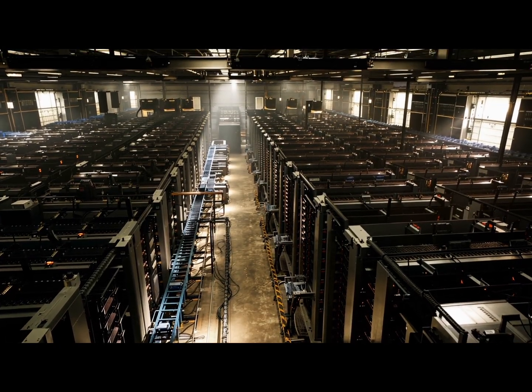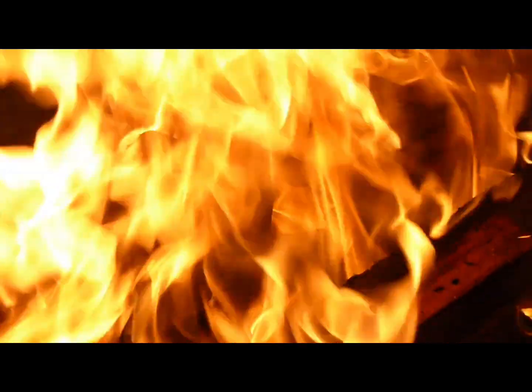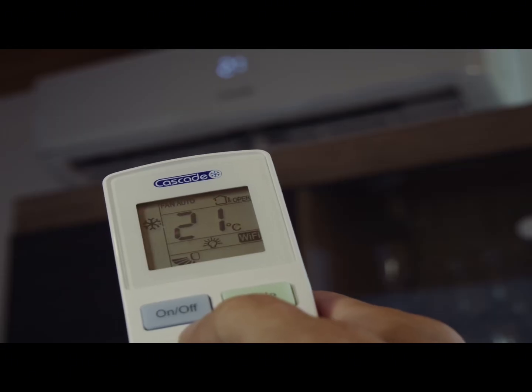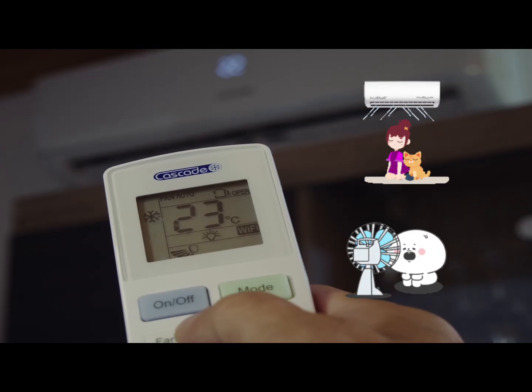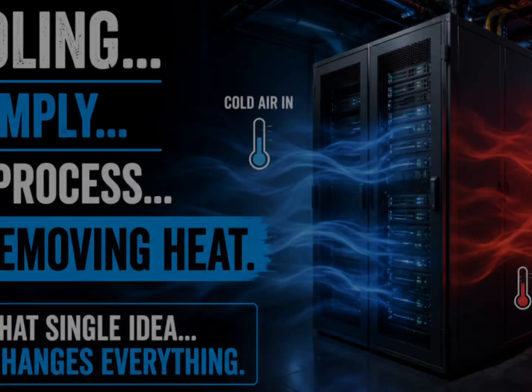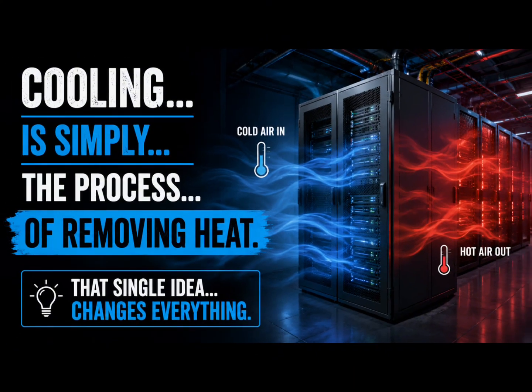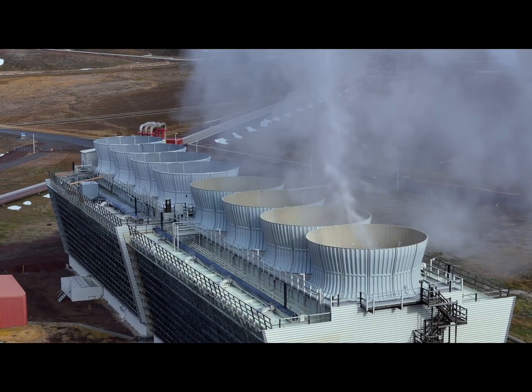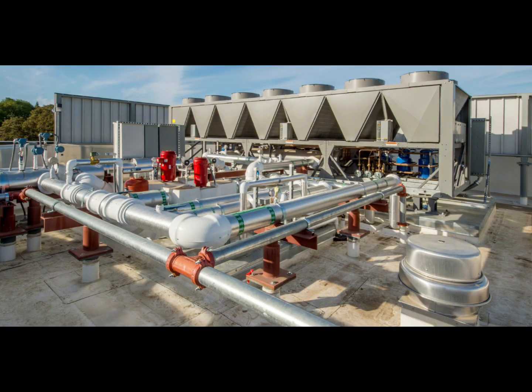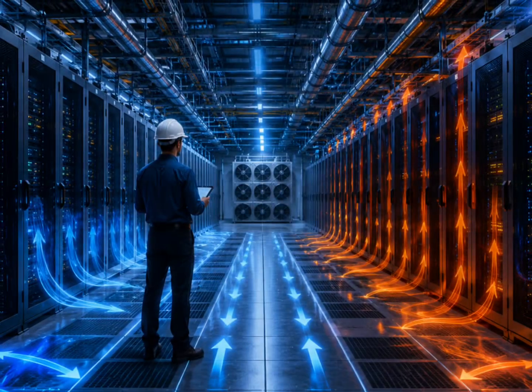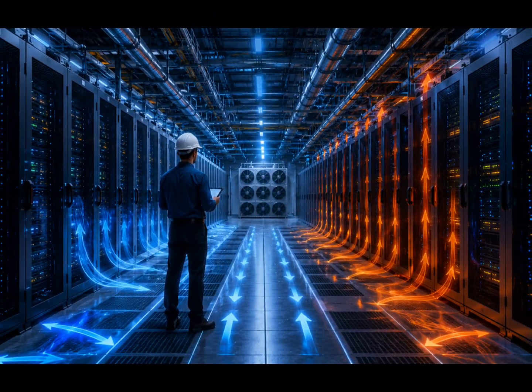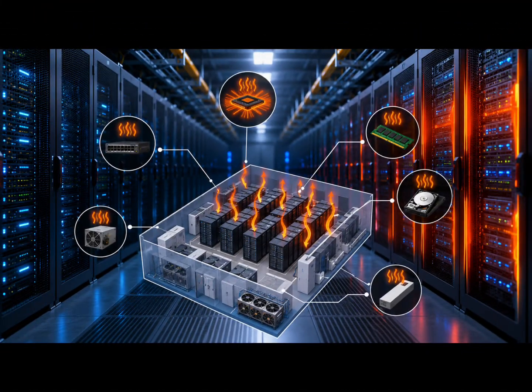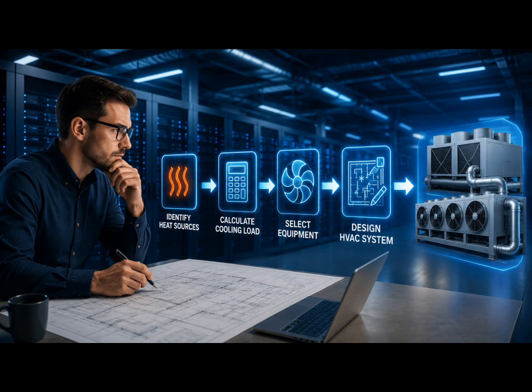The answer begins with one simple question. Where is the heat coming from? Many people believe cooling means producing cold air. It doesn't. Cooling is simply the process of removing heat. That single idea changes everything. Before engineers select chillers, before they size pumps, before they choose fan wall units, before they draw a single HVAC layout, they first identify every source of heat. Because if you know exactly where the heat is generated, you can calculate exactly how much cooling is required.